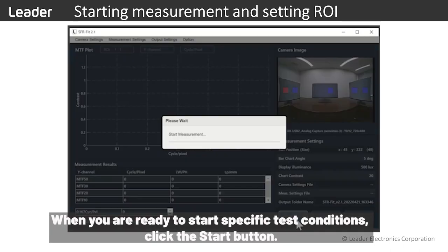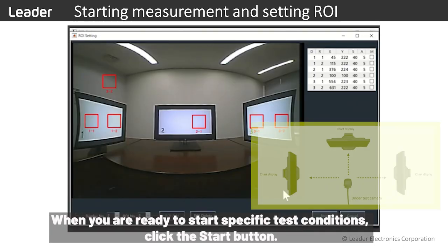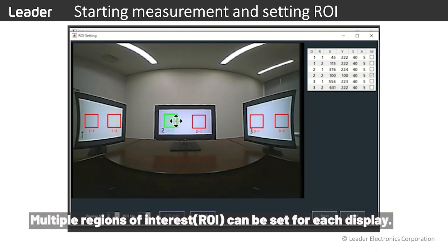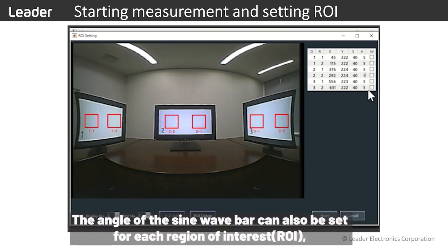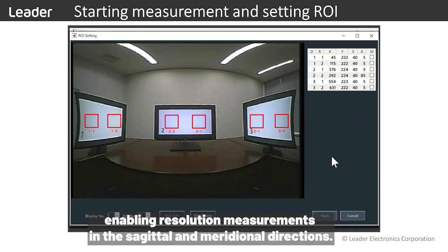When you are ready to start specific test conditions, click the start button. Multiple regions of interest can be set for each display. You can also set the angle of the sine bar chart for each region of interest, enabling resolution measurements in the sagittal and meridional directions.